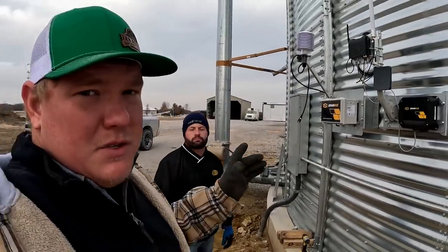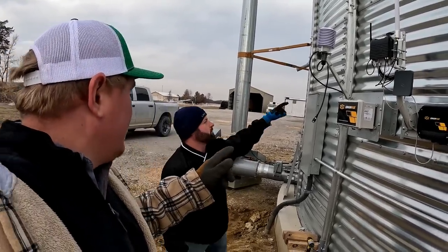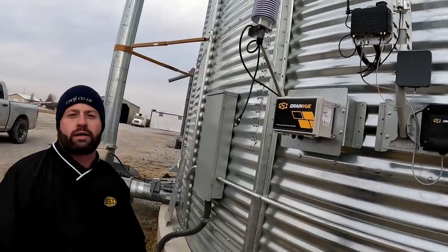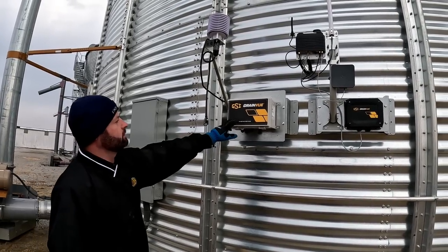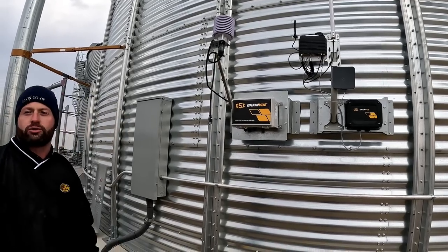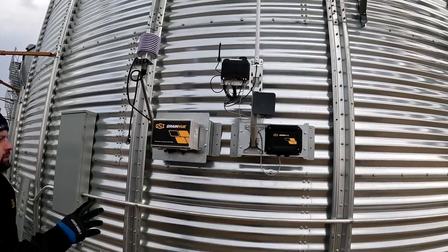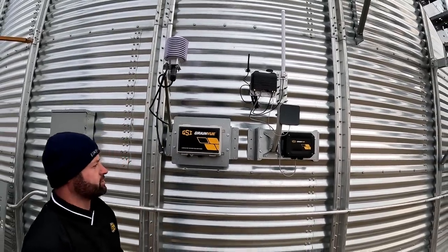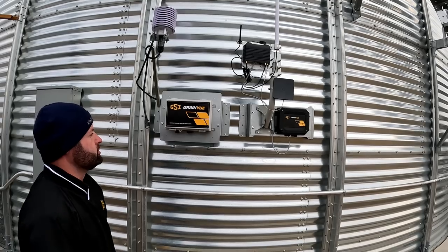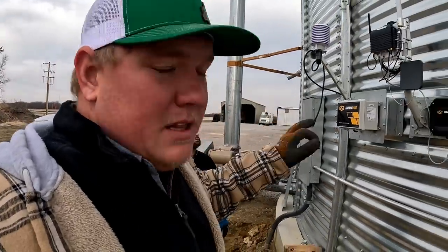Clint's with us today to finalize the GrainVue system install. The first module we hung on the bin is the weather station, which records outside conditions — outside air temp and humidity — so we know what conditions are outside at all times. That ties directly through a connection box into the FCM, the fan control module, which controls the fans automatically. Then we have the gateway on another bracket, which is a communication gateway to get that information remotely to the cloud so you can check or change settings, along with a power supply that powers that unit.